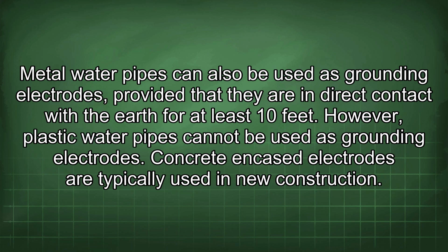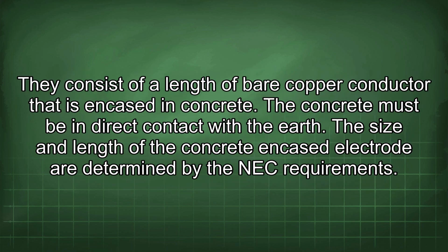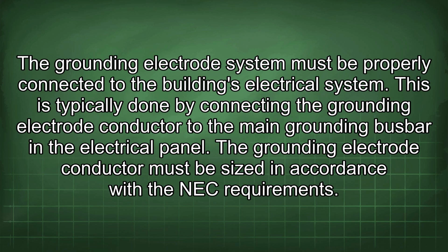Concrete encased electrodes are typically used in new construction. They consist of a length of bare copper conductor that is encased in concrete. The concrete must be in direct contact with the earth. The size and length of a concrete encased electrode are determined by the NEC requirements. The grounding electrode system must be properly connected to the building's electrical system. This is typically done by connecting the grounding electrode conductor to the main grounding busbar in the electrical panel. The grounding electrode conductor must be sized in accordance with the NEC requirements.